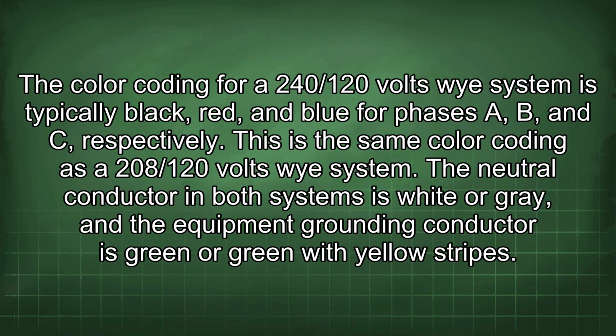The color coding for a 240/120 volts Y system is typically black, red, and blue for phases A, B, and C respectively. This is the same color coding as a 208/120 volts Y system. The neutral conductor in both systems is white or gray, and the equipment grounding conductor is green or green with yellow stripes.